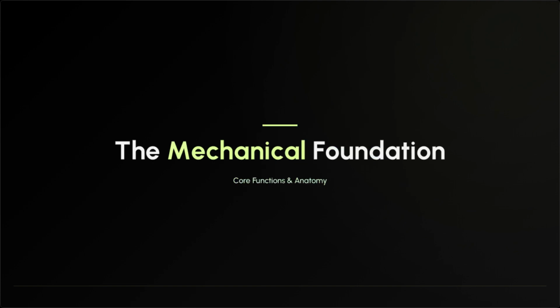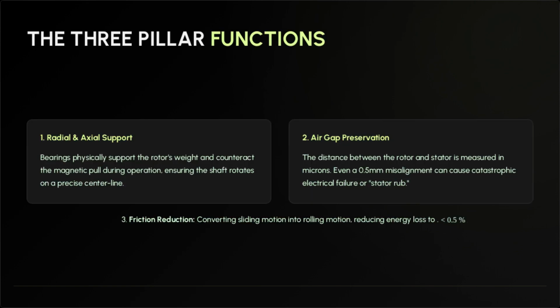First, let's establish the why. What is the mechanical role of a bearing within the motor housing? A bearing performs three critical tasks. 1. It supports the rotor and shaft. 2. It preserves the air gap, the microscopic space between the stator and rotor. If that gap vanishes, the motor shorts out. And 3.